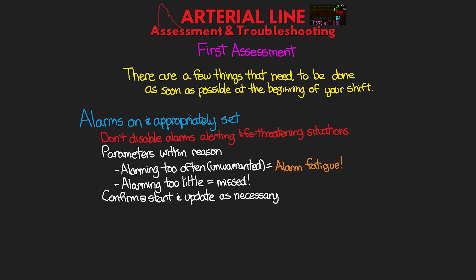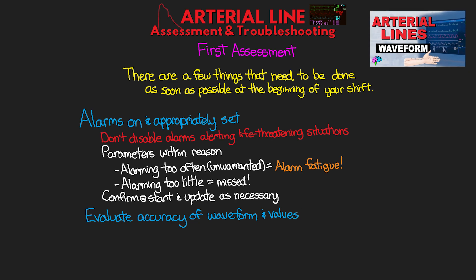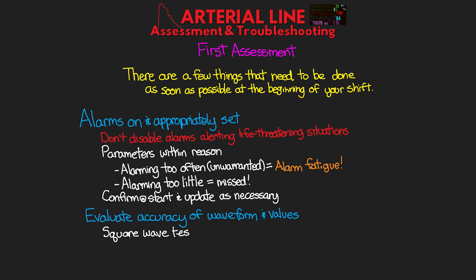Also, you want to evaluate the accuracy of your waveform and the values you have. As mentioned in the waveform lesson, perform a square wave test to check the proper level of dampening. And lastly, at the beginning of the shift, you want to zero and level your transducer.